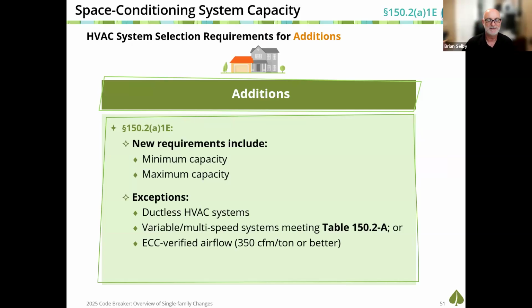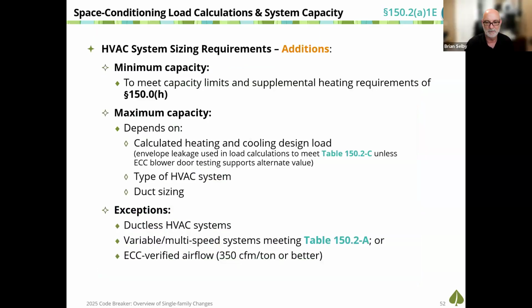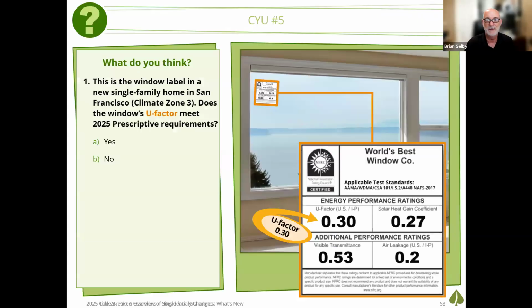Obviously, if that system is a ductless system, or if that system is using a variable speed or multi-speed fan system in order to meet that, and if you have verified the airflow being at least 350 CFM per ton or better, then those exceptions don't apply, or those requirements don't apply. Again, we're running into some time constraints here. We're getting kind of in the weeds with some of these limitations here.